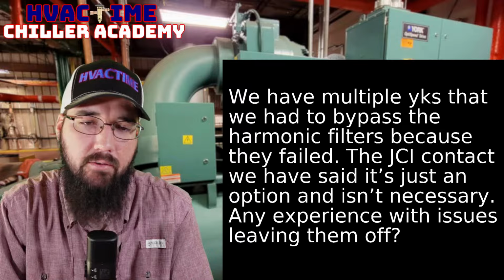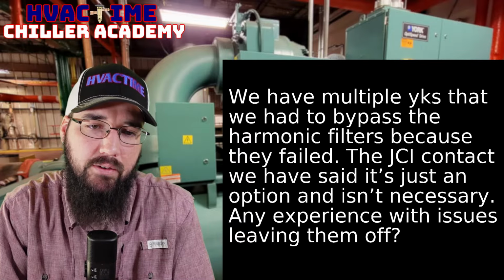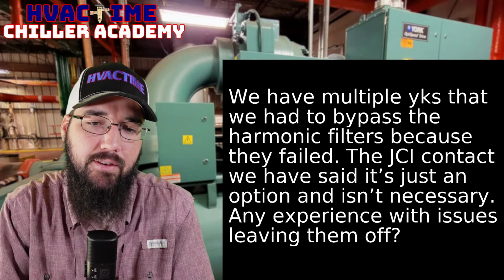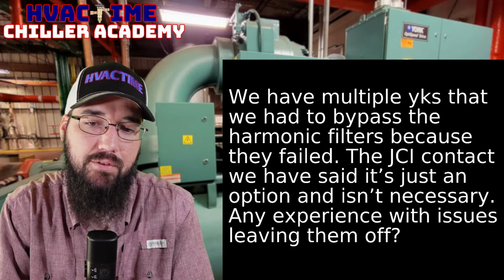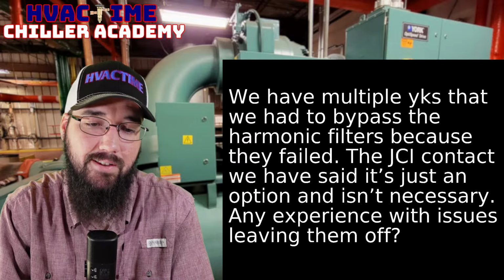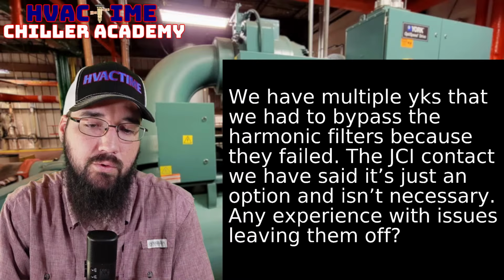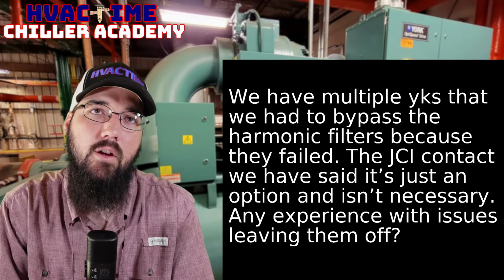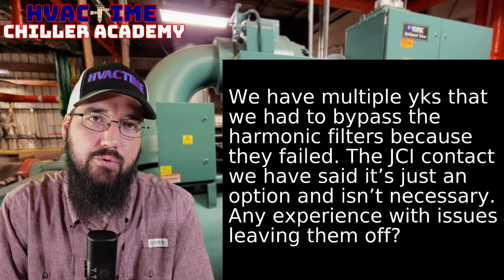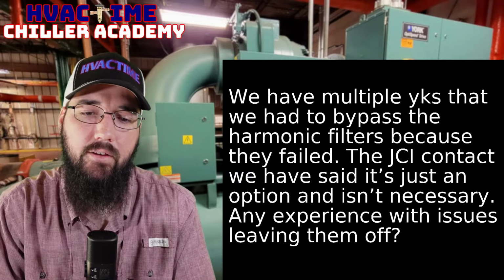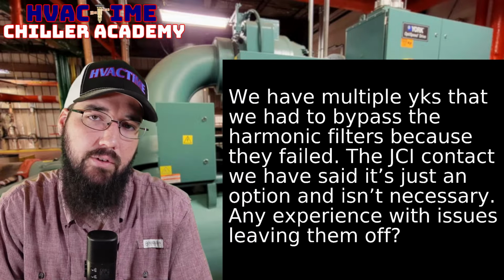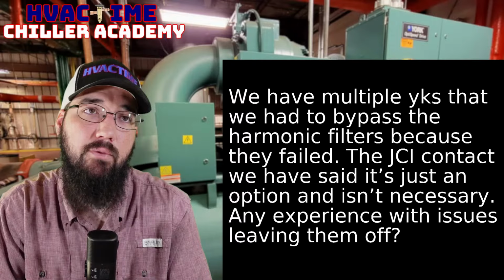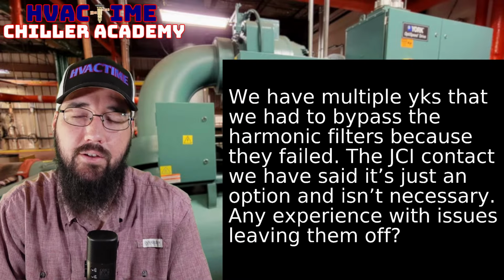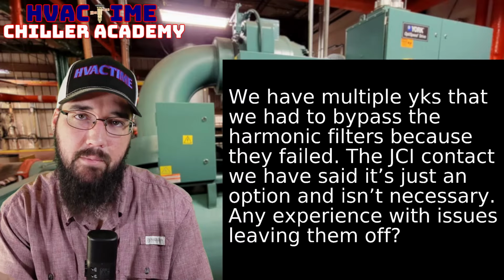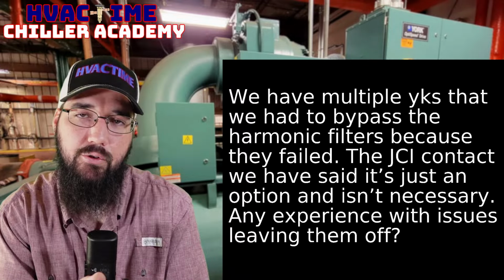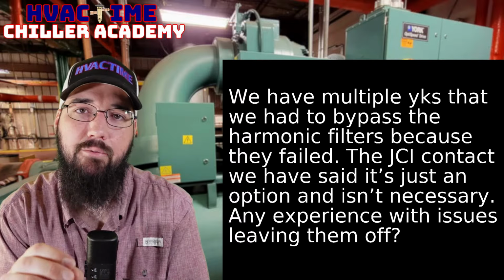So I'll dive off into this here. We have multiple YKs that we had to bypass the harmonic filters because they failed. The JCI contact we have said it's just an option and isn't necessary. Any experience with issues leaving them off? Have I had issues? No, I've not had issues with it. And especially these smaller tonnage, smaller drives, it's my experience it's more common to not have the filter than to have the filter. Now, keep in mind, even without the filter, you still have a line reactor.